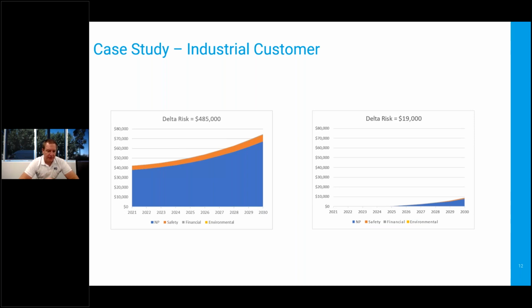Those sorts of manufacturing or installation issues - if you can identify the assets that are susceptible based on the manufacturer and type, or some combination of manufacturer, type, and year of install, then you can classify them as generically unreliable and apply a generic reliability factor to them. That pushes their health index up, which pushes their probability of failure up, which is then evidenced in the risk and the delta risk at the end.